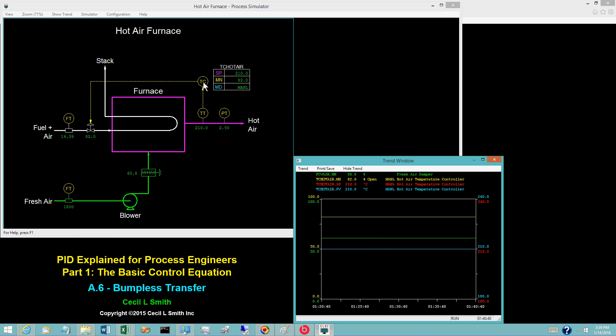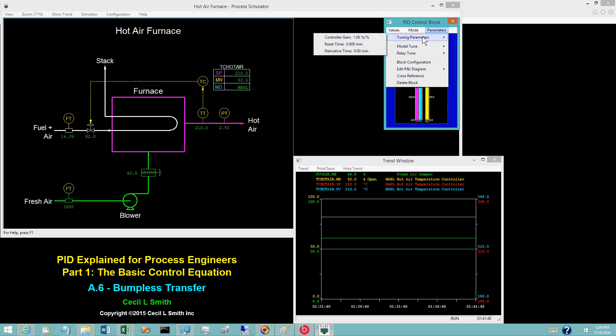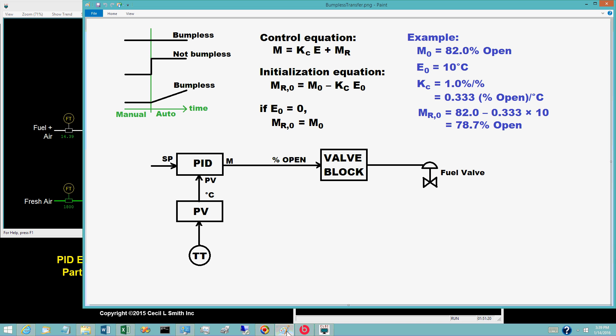Display the tuning coefficients for the hot air temperature controller. The controller gain is 1 and the reset time is 0.8 minutes — both proportional and integral modes are used. Both the PV and the setpoint are 210 degrees Celsius, so the control error is 0. For e sub 0 equal to 0, the initialization equation simplifies to m sub r at time 0 equals m at time 0.